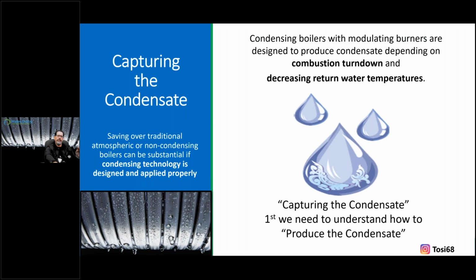So the turn down is key. Again, we go from a high to a low fire. We have a blower that's pulling our gas through and to the products of combustion, spark, air, and fuel. And now everything takes over. So we do want to see a wet neutralizer. That's when, hey, we got a boiler that's perfectly sized for the load. We have maybe even an undersized boiler, and now it's being tasked to maybe do more than it can, but it's always going to have enough, if not all zones are calling at the same time, right?